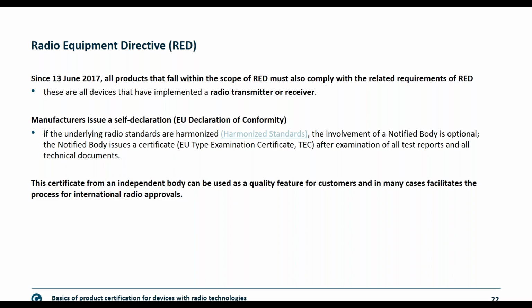So there are mainly two ways to gain market access in the EU. The one is self-declaration by a manufacturer. This is possible as long as you're using harmonized standards according to the Radio Equipment Directive. ETSI provides a list of those. We put the link in this presentation. You can have it afterwards. Second is you're using non-harmonized standards. Non-harmonized standards do not give the presumption of conformity to all requirements coming from the RED. And this includes the usage of a notified body. The notified body itself will issue a type examination certificate, a TEC, naming that your device was tested according to all requirements coming from the Radio Equipment Directive, but possibly not using harmonized standards.